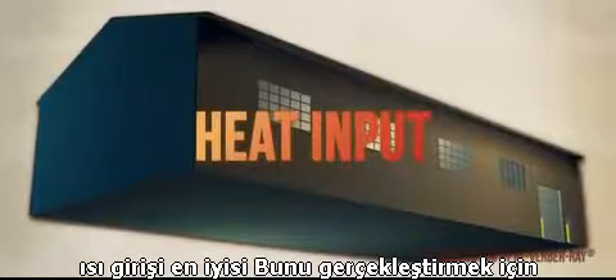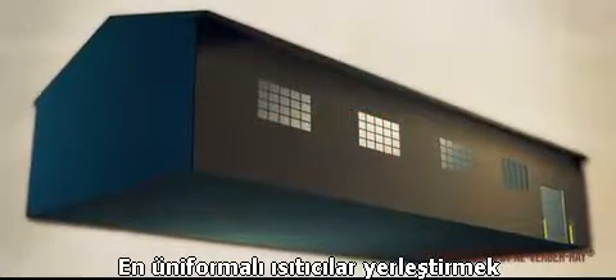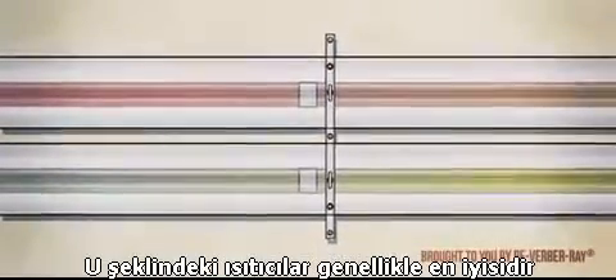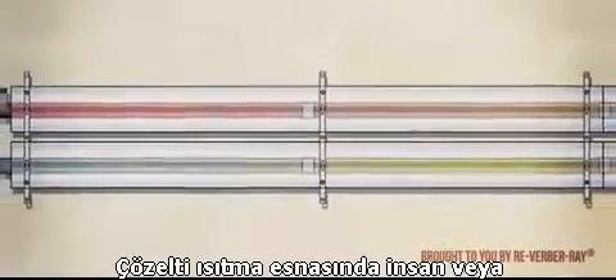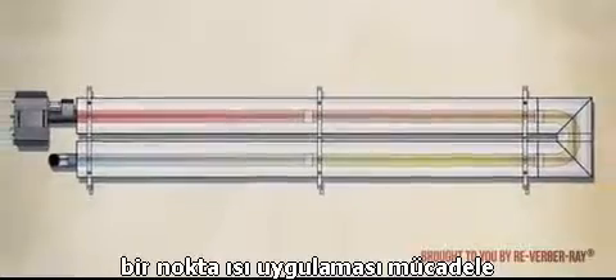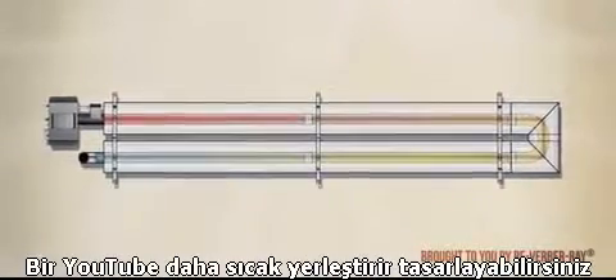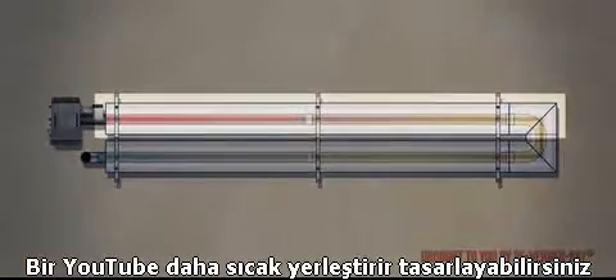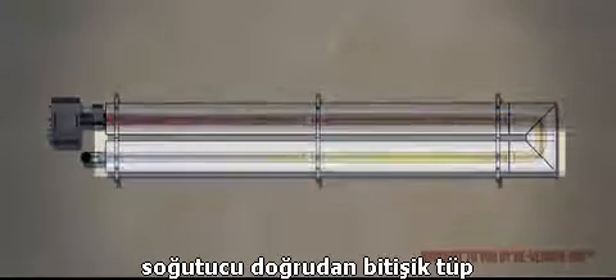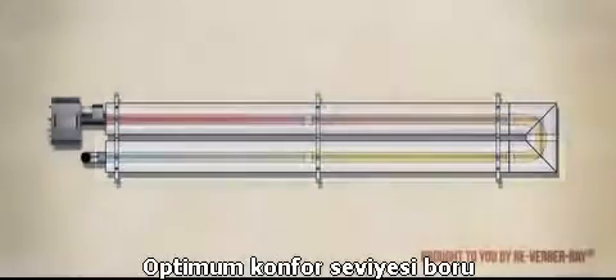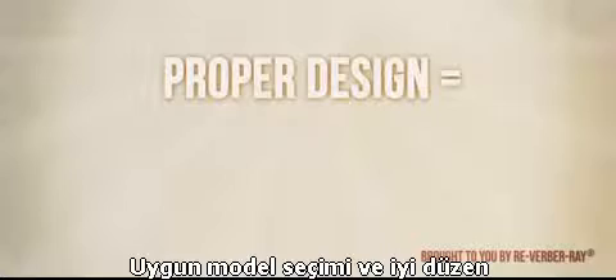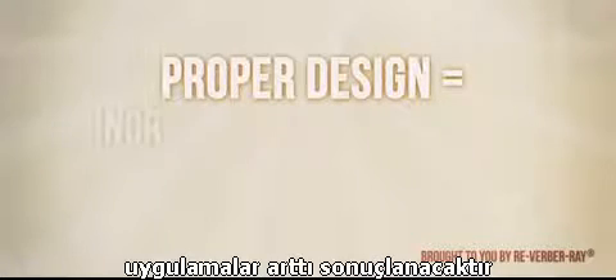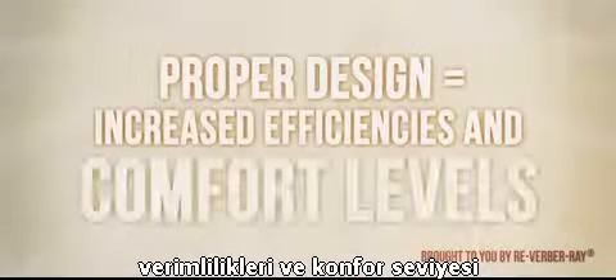To accomplish this, it's best to place heaters in the most uniform pattern possible. U-shaped heaters are often the best solution when heating people or when tackling a spot heat application. By design, a U-tube will place the hotter tube directly adjacent to the cooler tube for optimal comfort levels. Proper model selection and good layout practices will result in increased efficiencies and comfort levels.